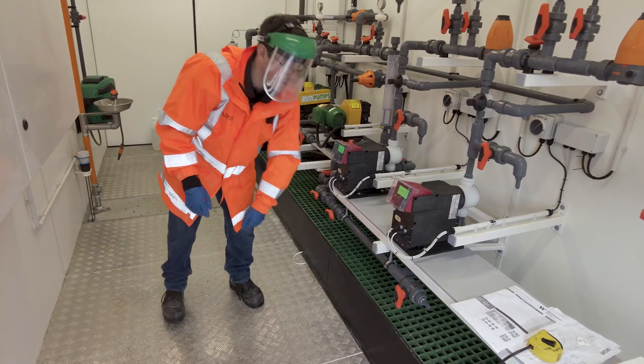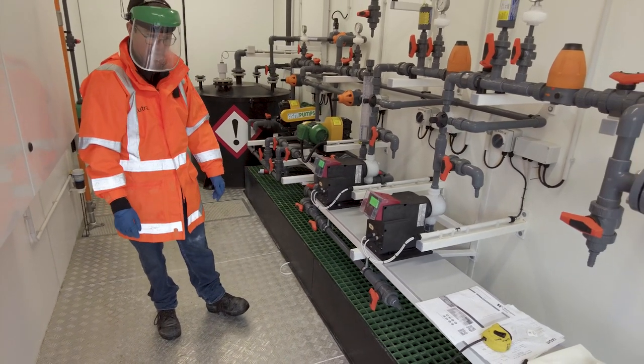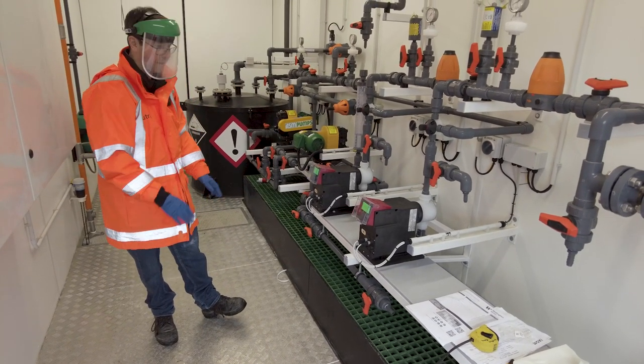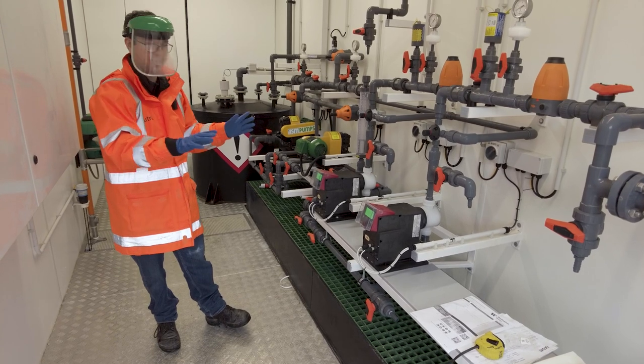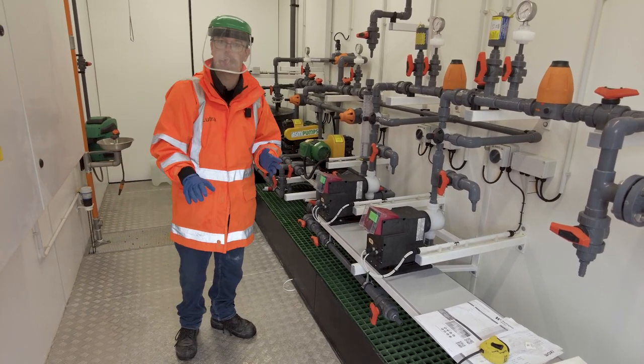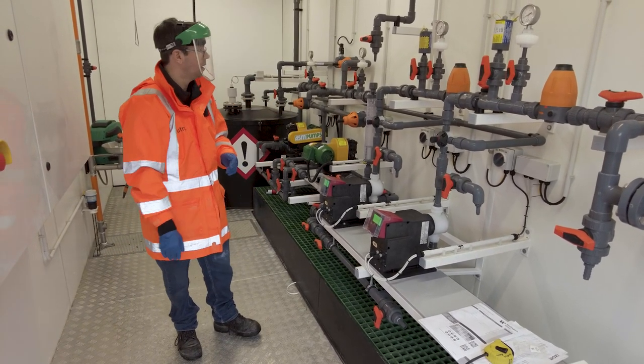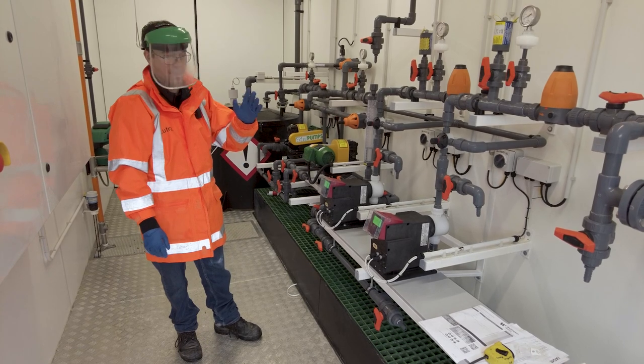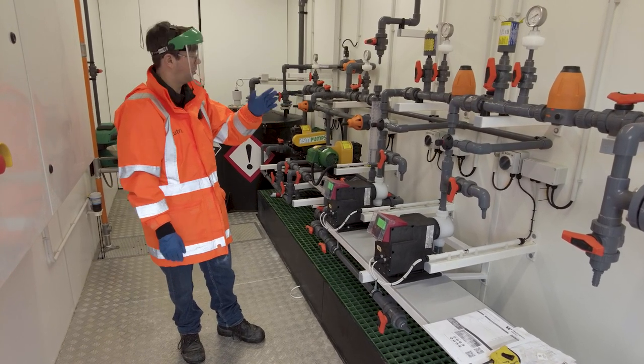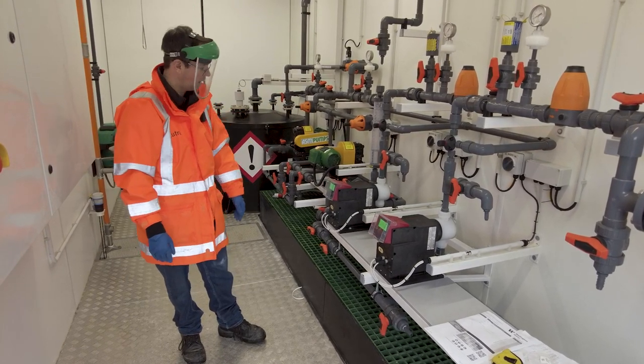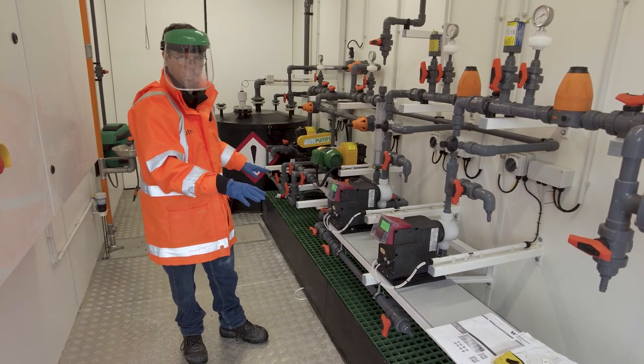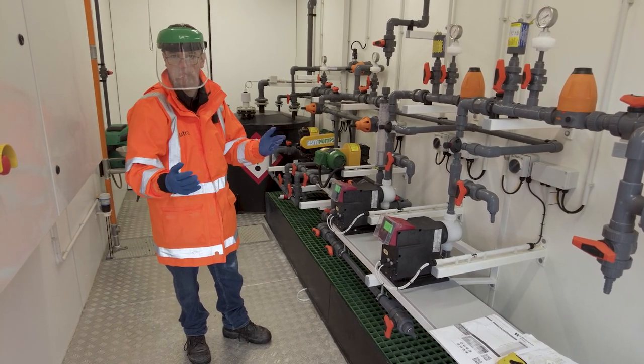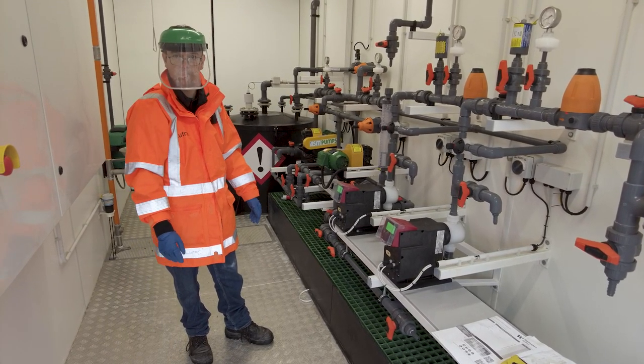Underneath all of the equipment we have this quite generous custom bund. The intent of this is that it's underneath at least 99% of all the fittings within the system, so if a leak or a breakage occurs at any of the bends or fittings, then it will go into this bund and a high level switch will indicate that there is a leak in the pipe work.